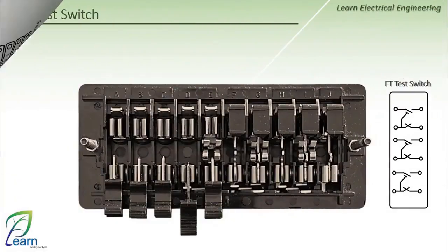The third thing is the test switch, and as an example, there is the FT test switch, or the finger type test switch. The test switch is used to quickly and easily test protection relays and measuring devices by injecting currents and measuring them using different injection devices. I can also inject through binary inputs and receive feedback from the relay as binary outputs.